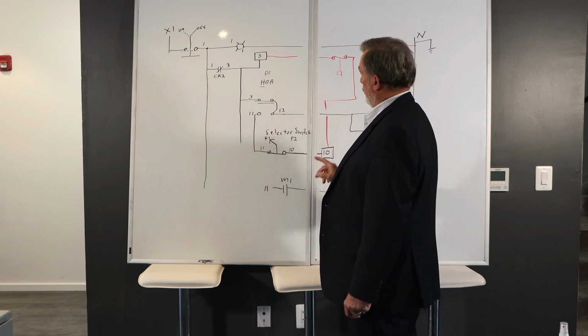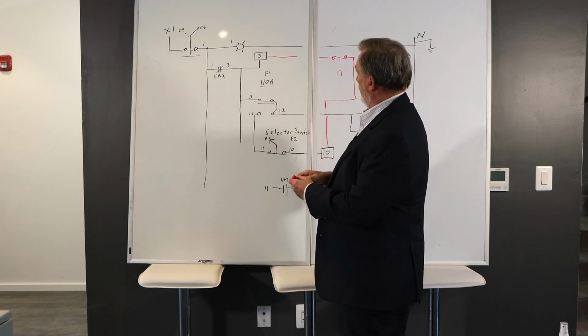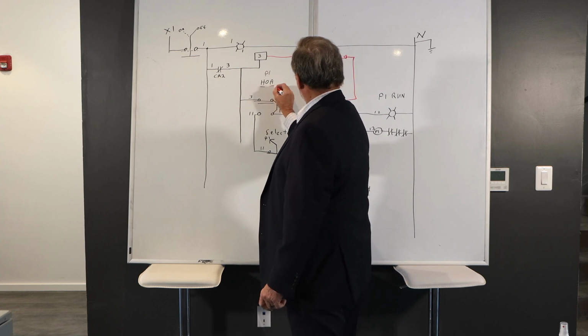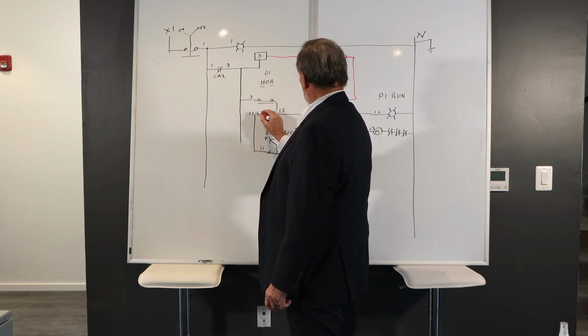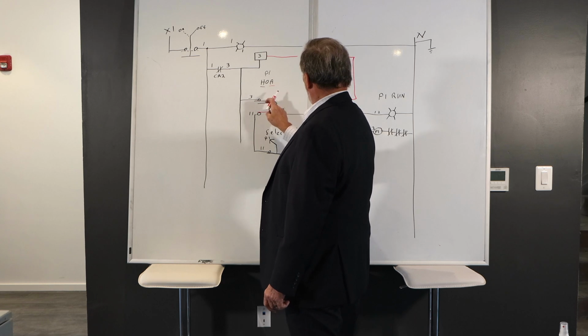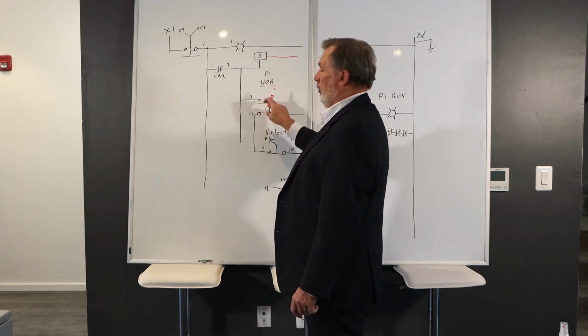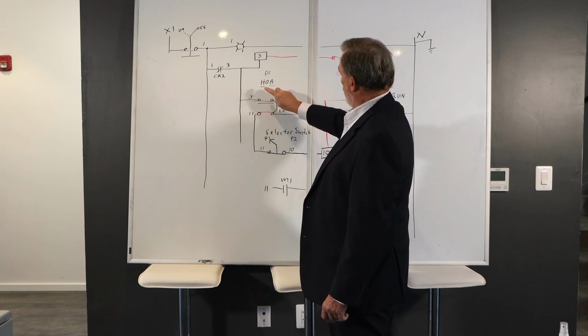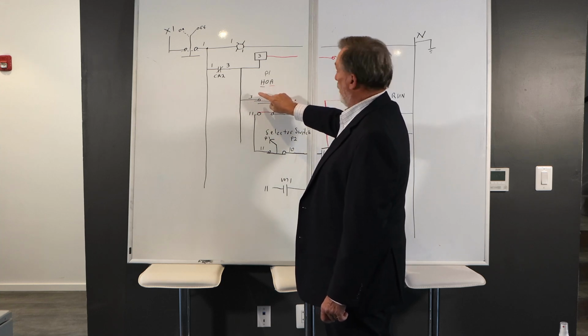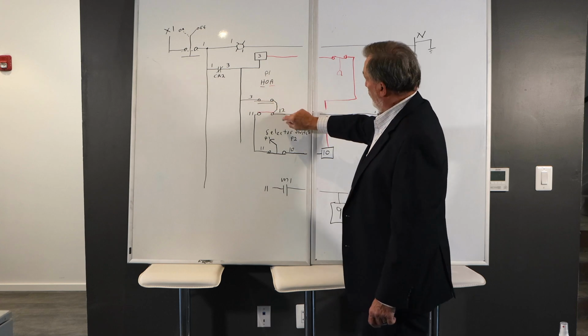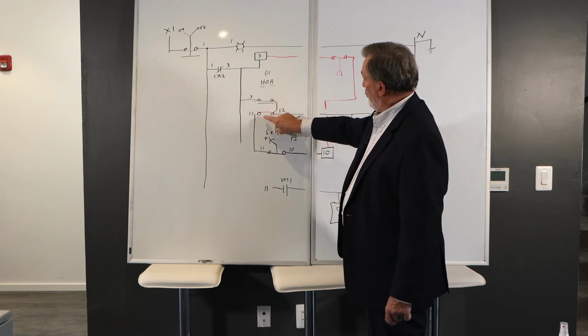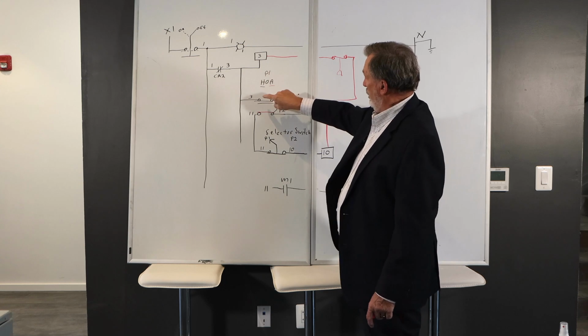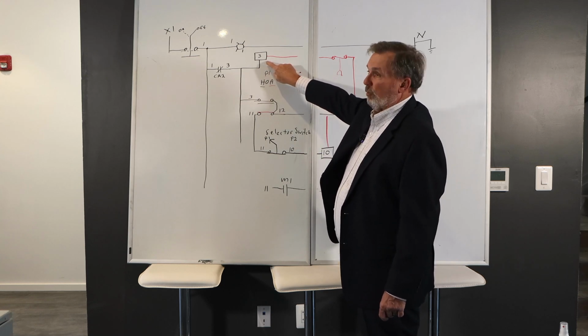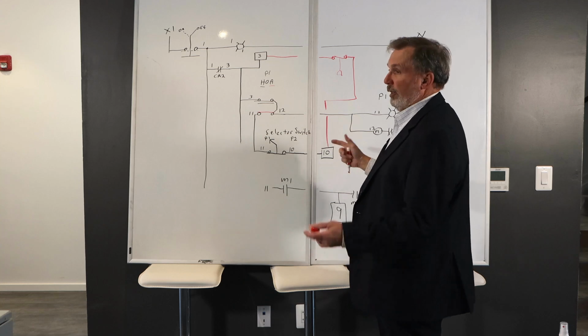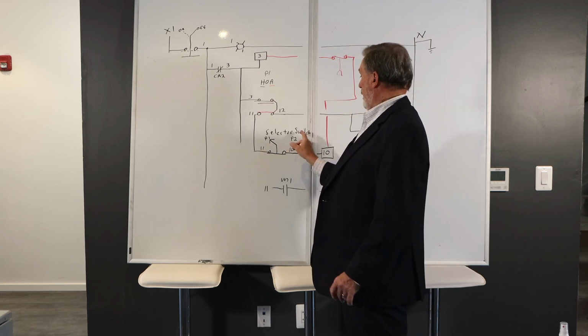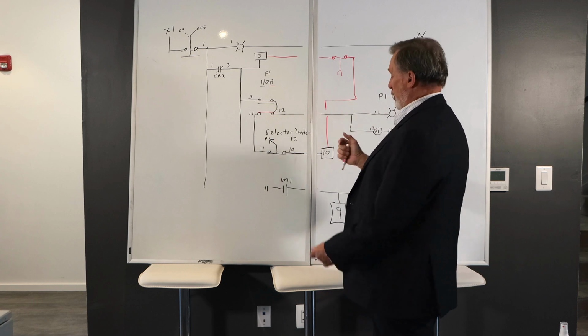Now let's take a look at this. When I go to automatic, I'm going to close these contacts right here. These are now open. Remember the brown here, if you can see the brown only makes contact when the switch is in the left hand or H position. Okay? But the automatic side is going to drop out my normal power feed, pick up my feed from number 3, go through a level switch, if you will, back feed through the selector switch for the pump, and then energize the coil.